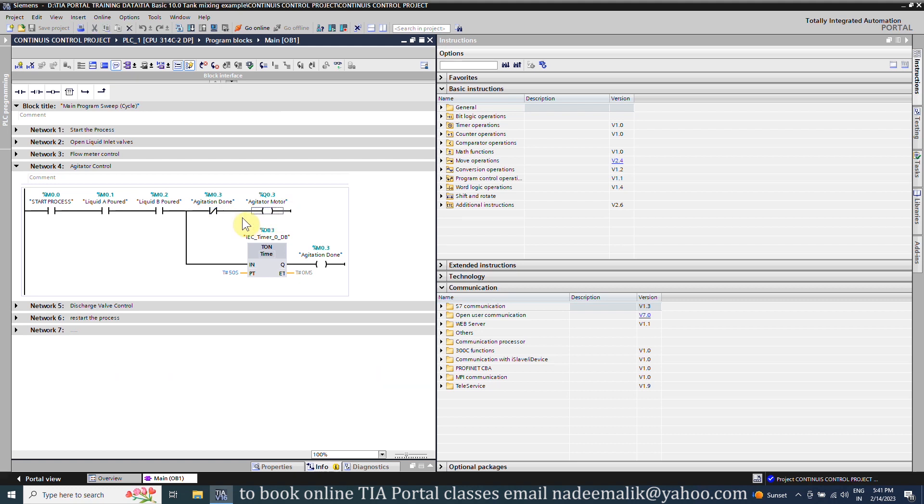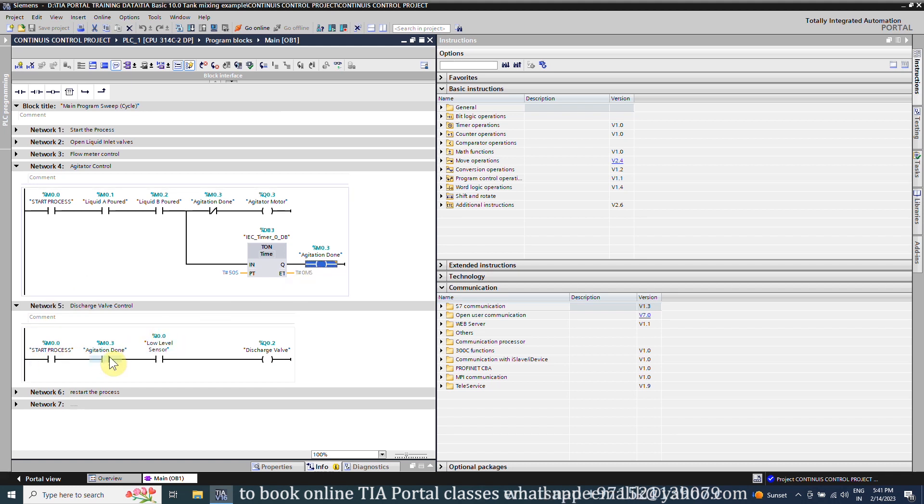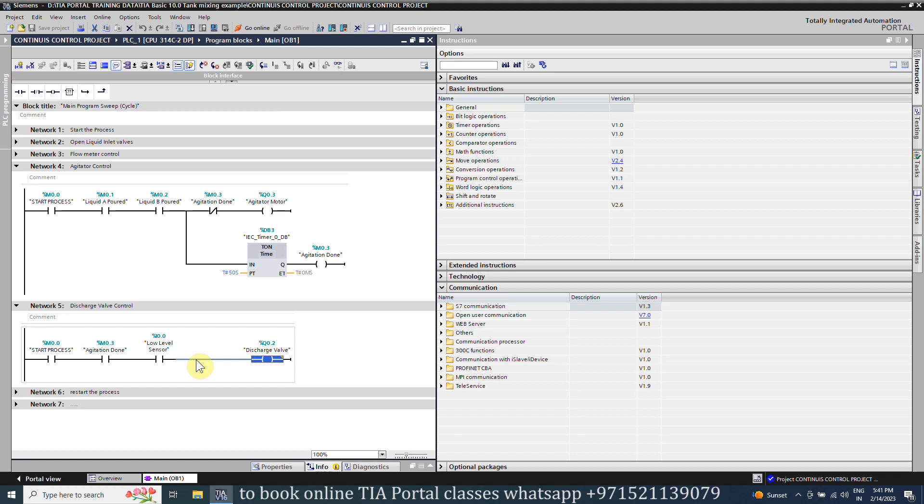In network number five we have a logic to open the discharge valve. As the agitation bit M0.3 turns on, it will turn on the discharge valve Q0.2. As the liquid level falls below the low limit probe I0.0, this bit opens and turns off the discharge valve Q0.2.